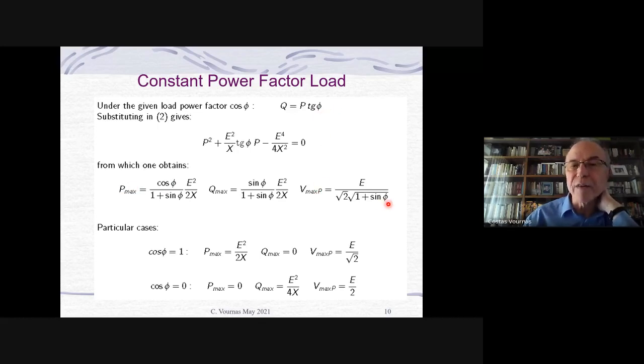And there is also the voltage where I have the maximum power. It's a bit complicated if I take a general power factor, but if I take the simple case where the power factor is 1, which means I have only active power, then the maximum power that I can transfer is half the short circuit power, and the voltage where I have the maximum power transfer is my feeding voltage divided by square root 2. This is roughly 0.7 times my feeding voltage E. And if I take the case where I have no active power, so cosine is 0, the maximum reactive power is 1/4 of the short circuit power.